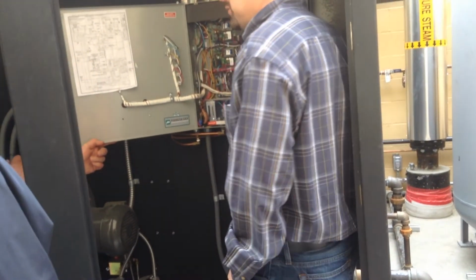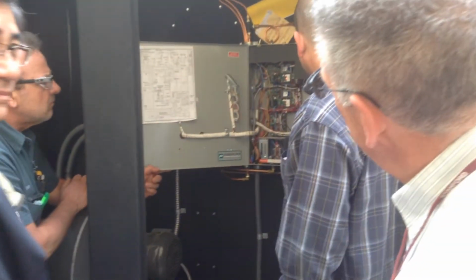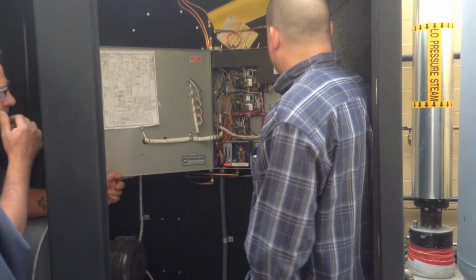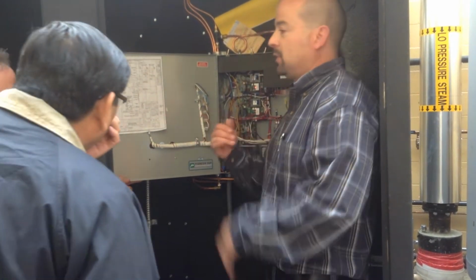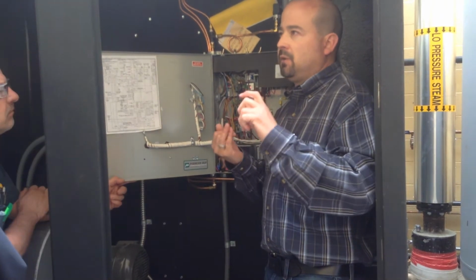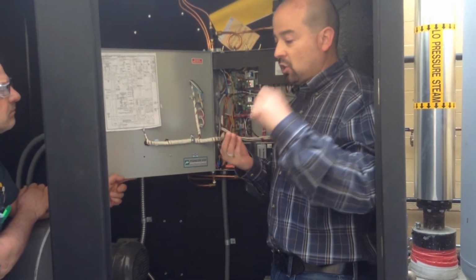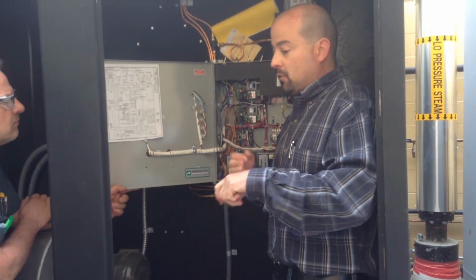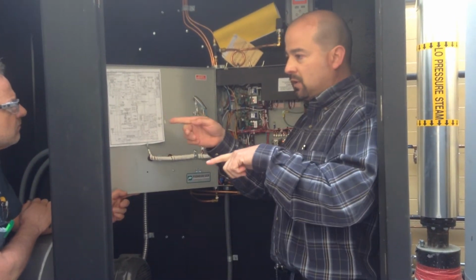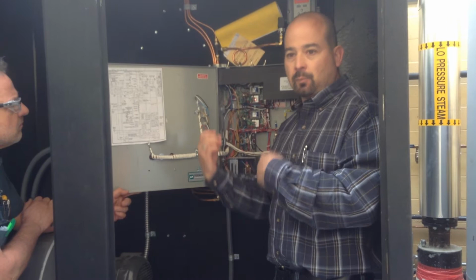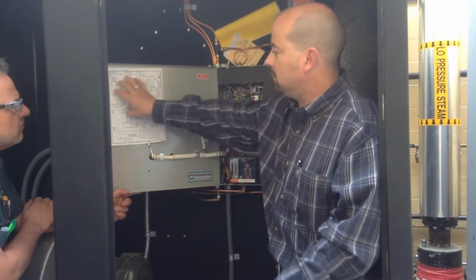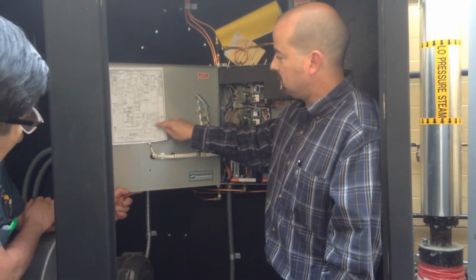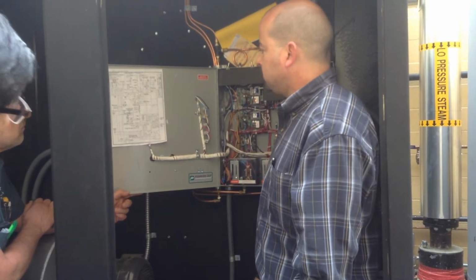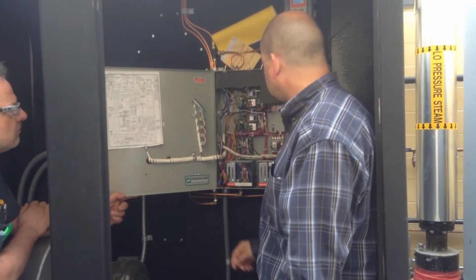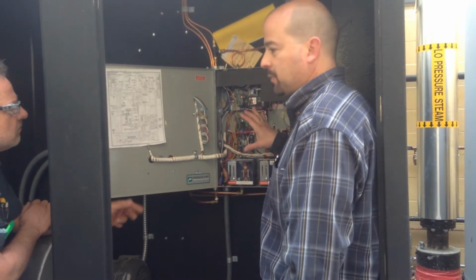What are the 4 wires that are not connected? Yeah. That's going to happen on Tuesday. Yeah. The relays, you'll see relays here. There's a relay for start-stop. There's a relay for status. There's a relay for alarm. There's also a 4 to 20 milliamp signal going out to tell the Delta V what the pressure is at the boiler. And it's all on this schematic here. Everything here. These relays, those are all the relays. So got a lot of functionality here. Any questions before I close the panel?